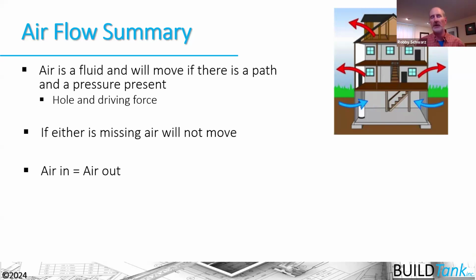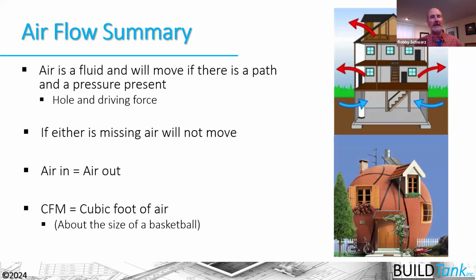So to summarize, air is a fluid, just like water's a fluid. Air in equals air out, but I need a hole and a driving force across that hole. The driving force is also called a pressure difference across that hole. If either is missing, then air won't move. So we know for a fact that air in equals air out. And so I can put a measuring device on a bath fan and measure the amount of air that's flowing from inside the house to outside the house. I know somewhere air's coming back in through that building thermal envelope at that same quantity. So a cubic foot of air is about the size of a basketball. We can keep that in mind as a reference point.